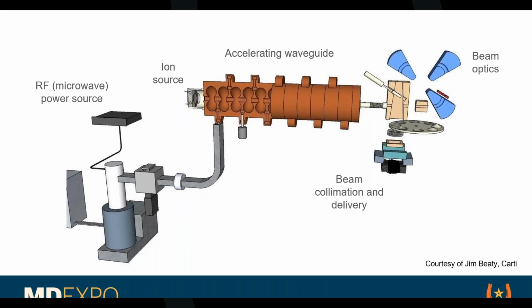So we need what's called a beam optic system. We have a bending magnet where we redirect the beam towards the patient, and then we have to make that beam into a beam which is useful. So now we have the raw X-ray beam. The intensity is varying. It's a good beam, but we need to shape it so that it's useful for the patient. So we have filtering, and then we have collimation to make it the right size and so on. This all goes down in the area closer to the patient head. So there's a lot of parts. It seems complicated, but if you take each one by itself in a linear fashion, it's not that difficult. That's the main way of doing that.